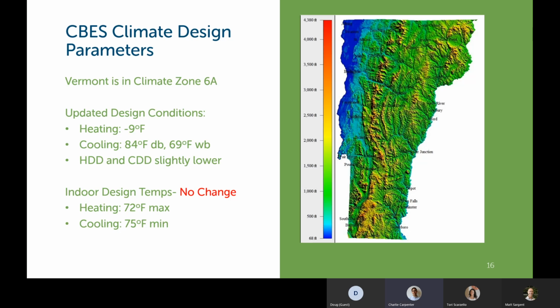The heating design condition has been changed. It's slightly warmer than it was in the previous version, or the RBES, which is minus 11 degrees Fahrenheit. It's been warmed up to minus 9 for the commercial buildings, and similar cooling, dry bulb and wet bulb design temperatures. I don't have them listed, but the heating and cooling degree days are both a very slight amount lower for the 2020 CBES than 2015, and same indoor design temperature ratings for load calcs as the previous code and RBES, 72 for heating and 75 for cooling.